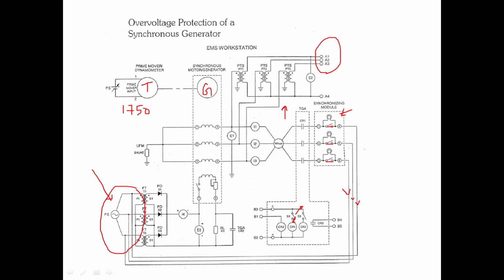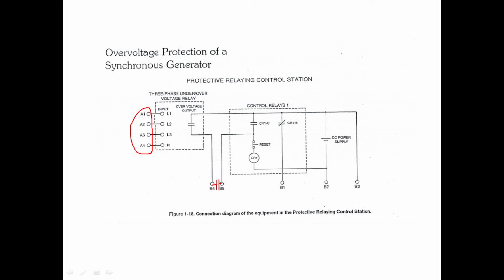Now across B1 and B2, we have only the CR2 contact. Here we are using CR1 to produce the fault. So this is CR2, and then here we have a switch, and this is the coil of CR3. So this is how it is connected. Under normal condition, this CR3 contact will be open, so this contact is also open. The only direction the current can flow is through CR2, so CR2 will be energized.